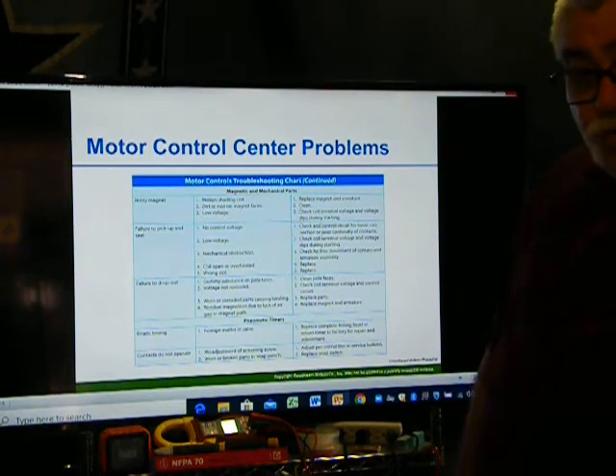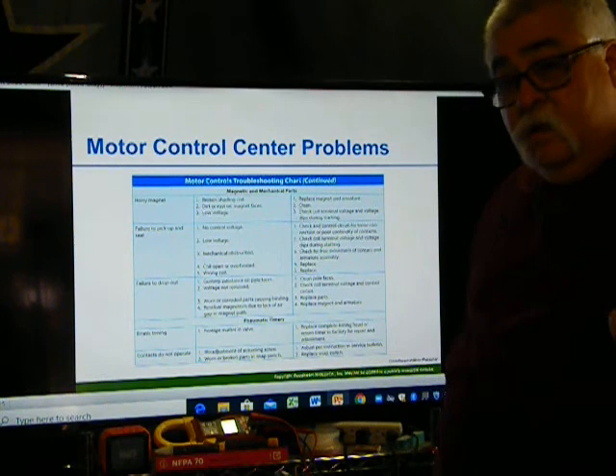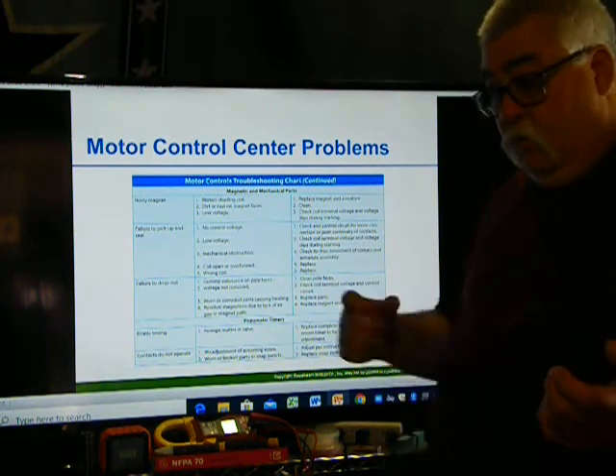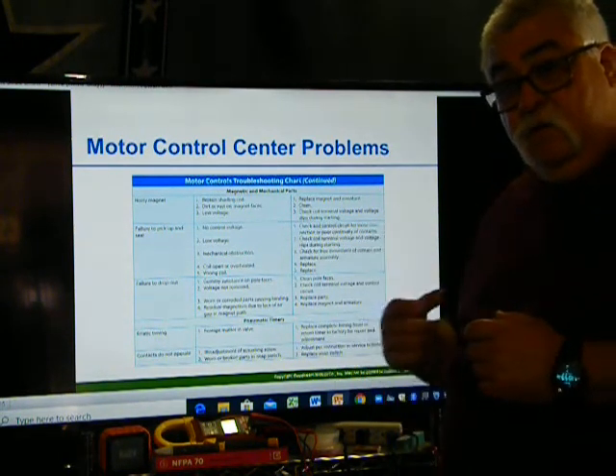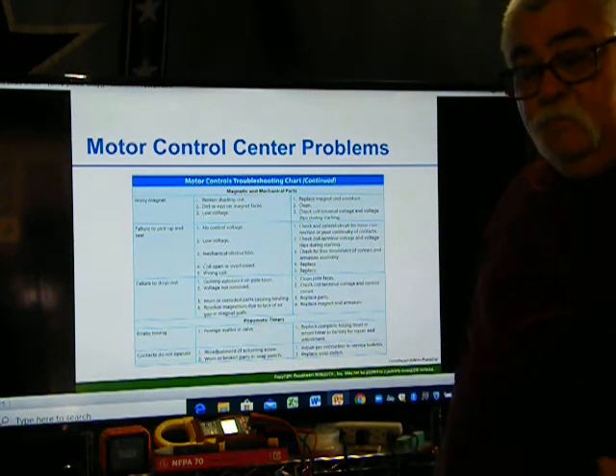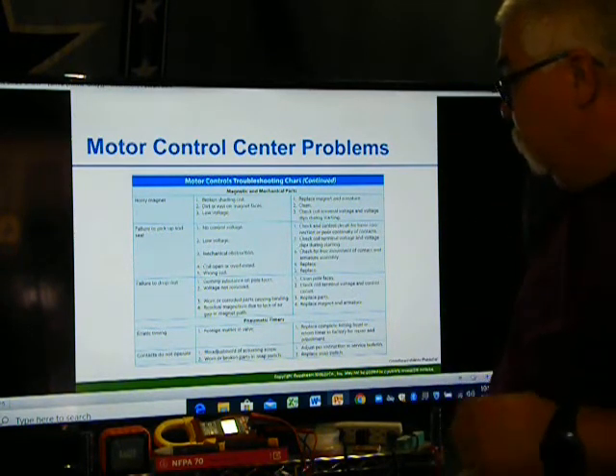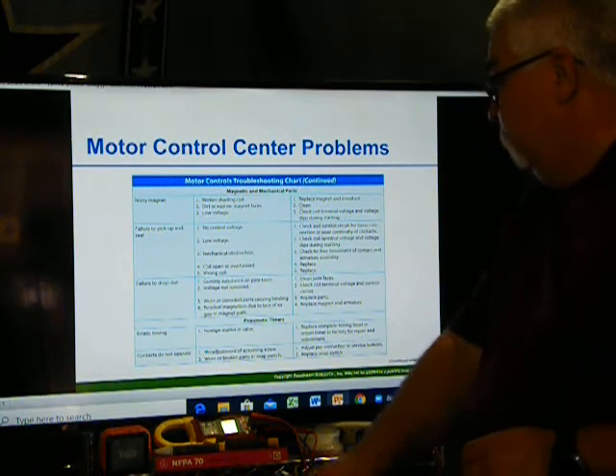I've got one coil, it's 120 volts. I have another coil that's 220 volts. Well, if you put a 220 volt coil on 120 volts, guess what? The coil's not going to close because it's not designed for that. The magnetic field is not going to be strong enough.